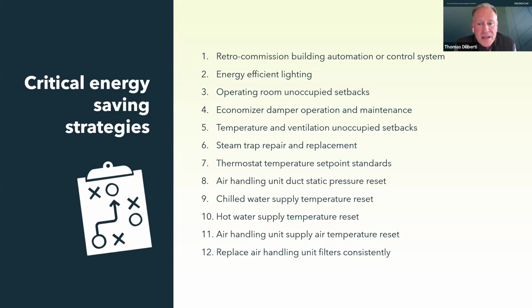There's something called a static pressure reset, where it changes the pressure based on the time of day or based on the temperature conditions, and it should be implemented as a way to save energy. That's a little trickier, more sophisticated, but it's a great opportunity.